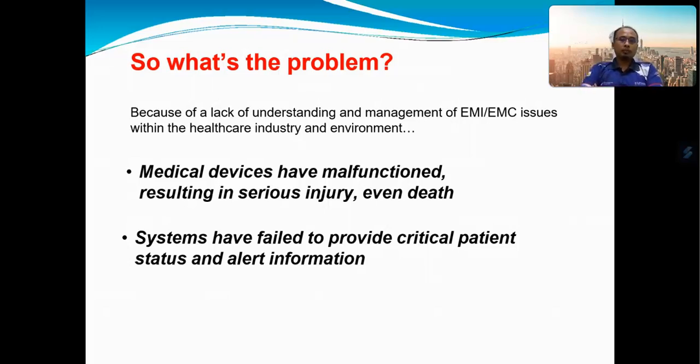So what is the problem related to the EMI and also EMC? Because of lack of understanding and management of EMI and EMC issues within the healthcare environment, normally we can find that many medical devices malfunction, resulting in serious injury or even death.